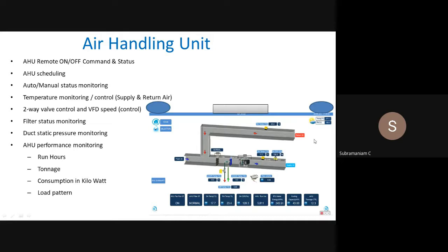So this is your graphic screen, what you create in BMS. This is your return air. This is connected to the AHU, which is the filter section. This is the chilled water coil section. This is your fan, supplying air to all the VAV boxes. Whatever field devices you have put here, all those things we can get on the graphics.